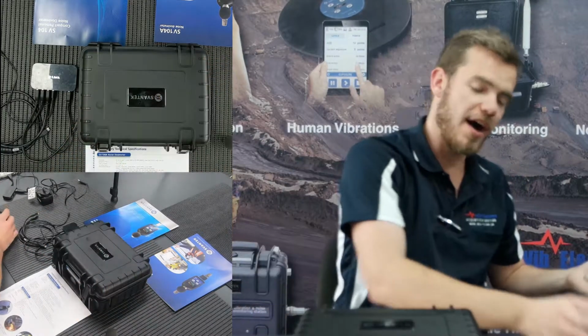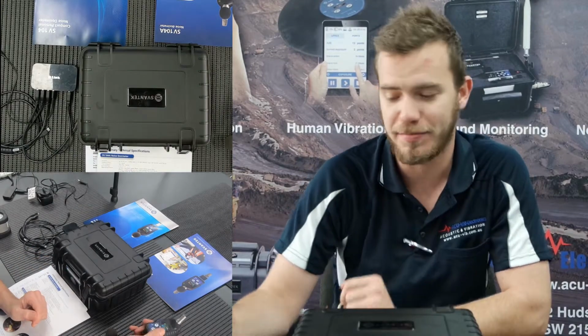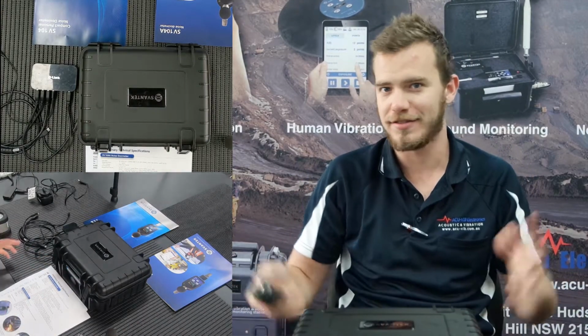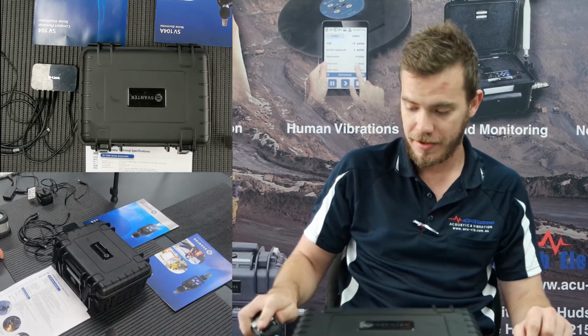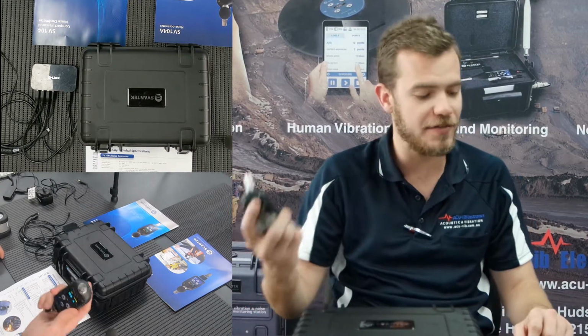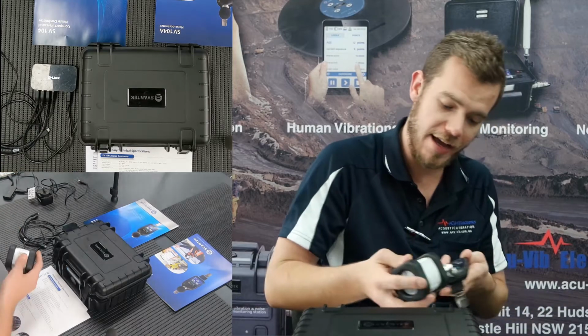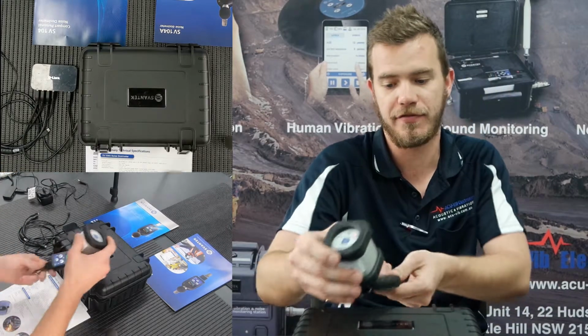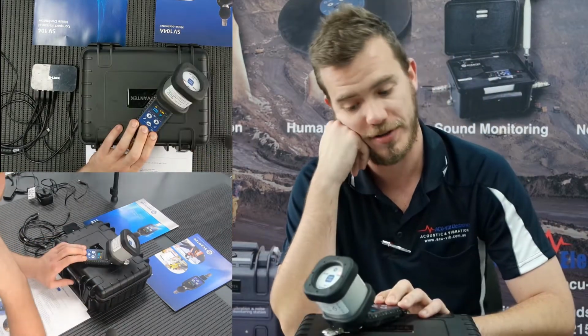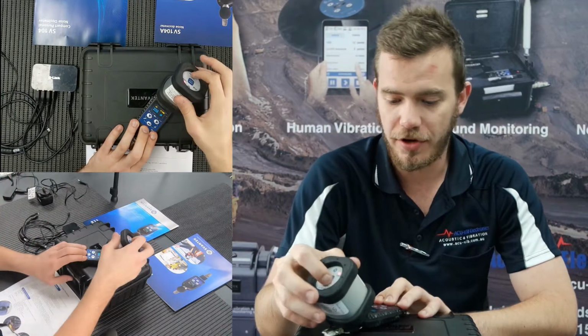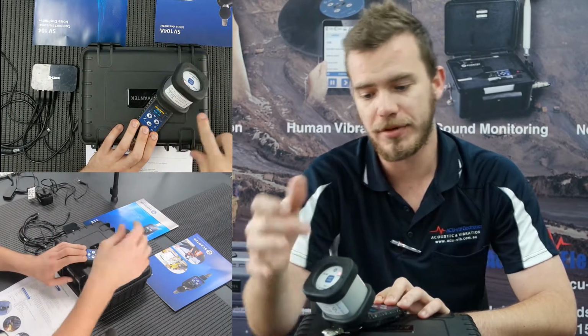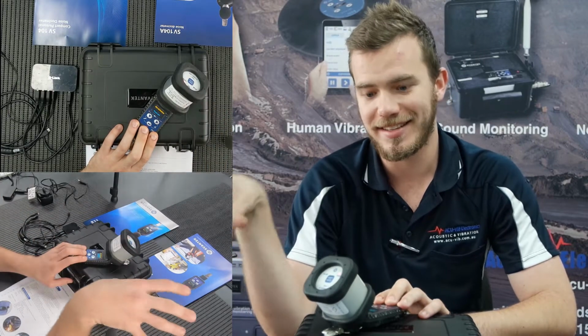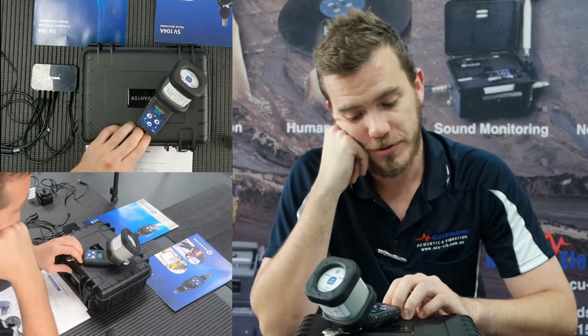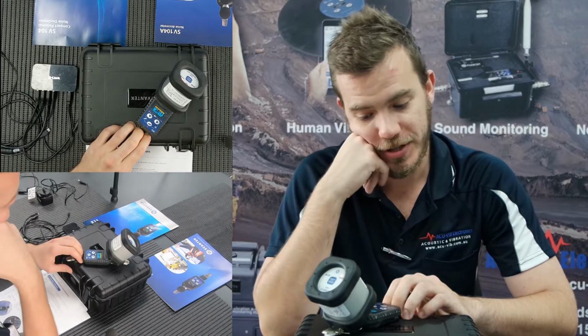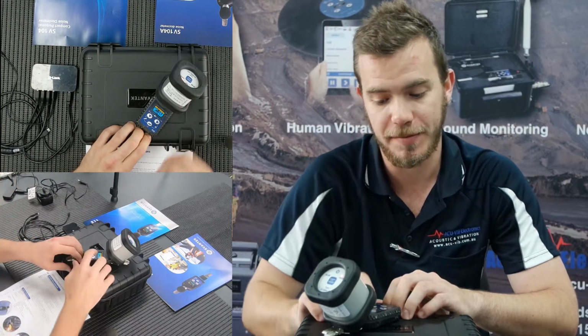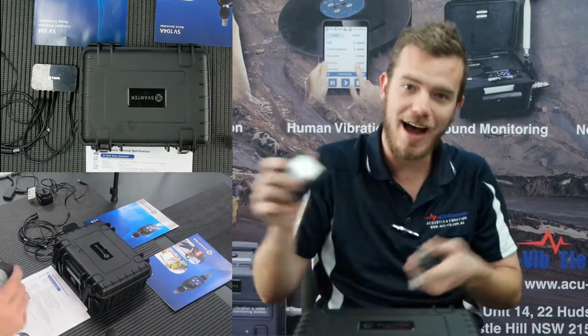I'm going to pop it off. Now for argument's sake, I was shown this by someone overseas. I don't recommend doing this, but it can be done. So basically if I tap the microphone, and I would never tap any other microphone that we have at Acu-Vib or at Svantek, just due to the fragileness of pre-polarized microphones, that sort of thing. So once again, the instrument's going to sense that there is an input level, 114 dB, which I've set inside the software already. Once this goes through its internal auto calibration, it's going to give us a factor of 0.4 dB. Let's accept that. It's still within tolerance after me bumping it.